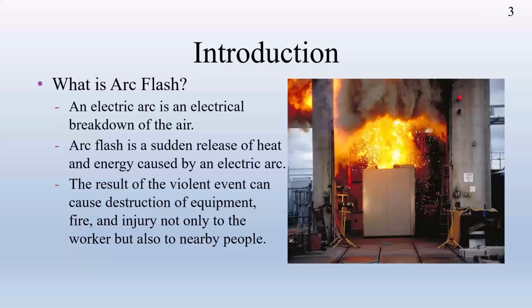When you talk about arc flash in a regular electrical installation, you have enough insulation level, so it will not create any leakage current or any path between two conductors. However, in some cases, sometimes we call it a screwdriver alert, somebody during the work drops a tool and creates a short circuit. Once the short circuit happens, it is going to create a lot of heat, and the heat will then ionize the air. That will create the breakdown of the air, and the arc flash starts this way. Once the air is ionized, even if the tool bounces away, the current continues.